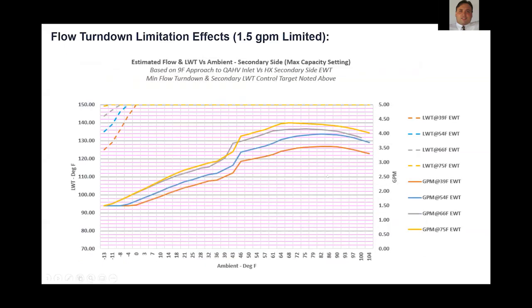This is just representative of a phenomenon you can see in these systems if you don't have proper flow turn down. This is looking at our equipment, where you were limited to 1.5 GPM instead of 0.8 GPM or lower, and you were targeting 150 degree water temp. These solid lines represent your water flow rates, right? And your bottom axis is your ambient conditions. So these are just different water flow rate requirements at different entering water temperatures into that heat pump water heater. As ambient temperatures drop, your water flow rates must drop in order to maintain that 150 degree water set temp target in this example.